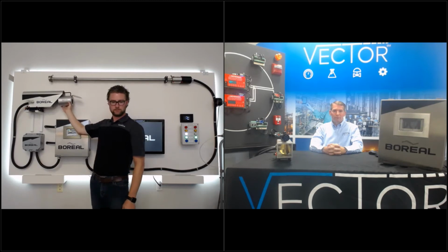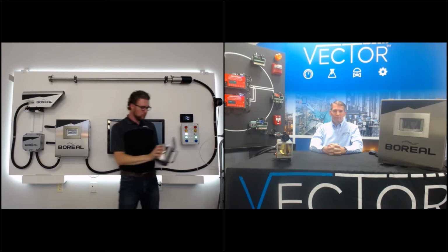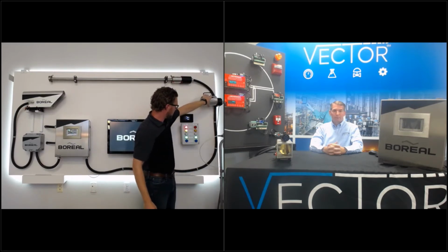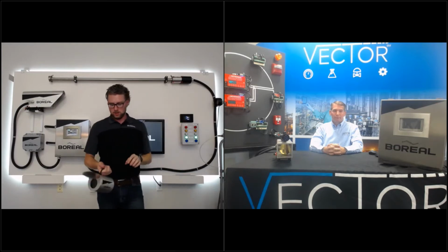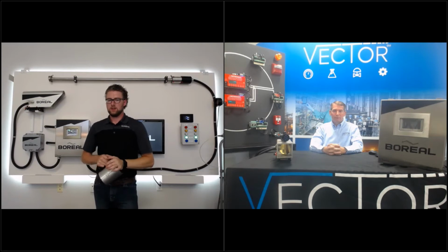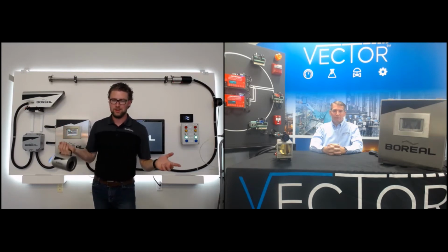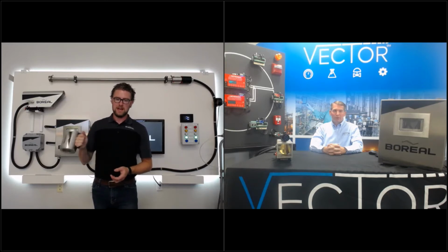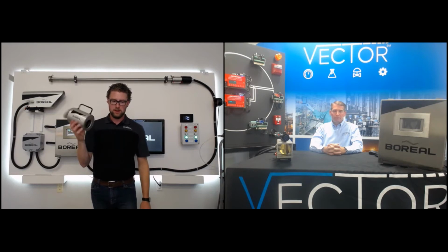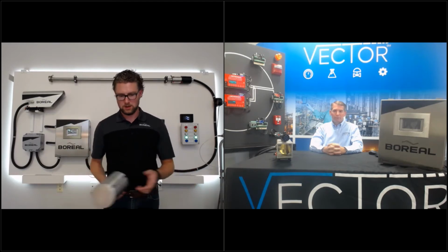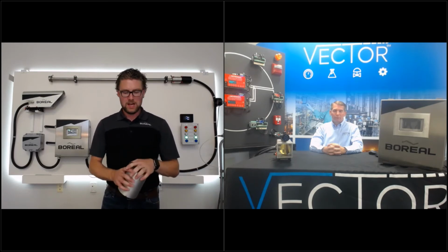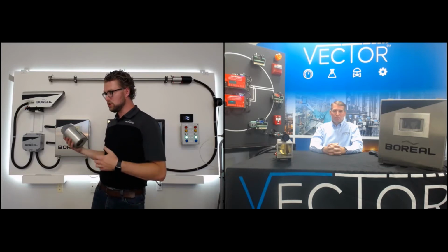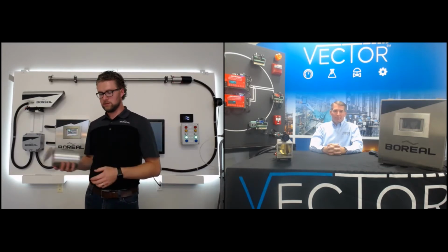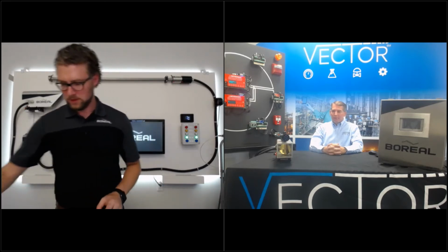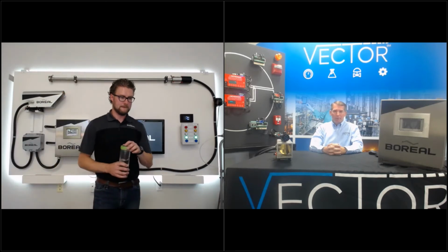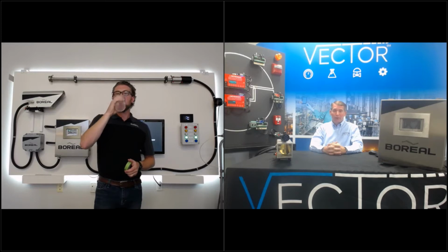But then we also have the ability to come through and place this within the active measurement path as well. Just because this does not require any user intervention or calibration does not mean that this system is a completely set and forget system. So if you still want to have a preventative maintenance tool, we do have this optional accessory. Very easy to use, very easy to conduct those tests as well. Chad, do you have anything to add to the functionality of the product, the calibration, the internal reference cell, or the fail-safe nature of this? Well, like you said, honestly, this is probably one of the most maintenance-free gas detectors you'll find anywhere globally.